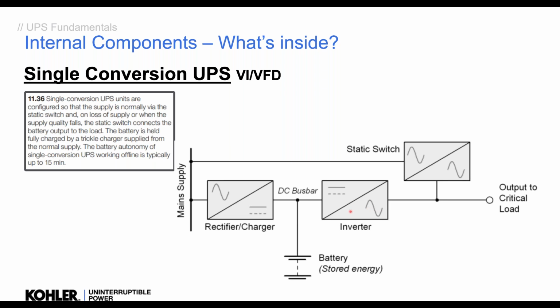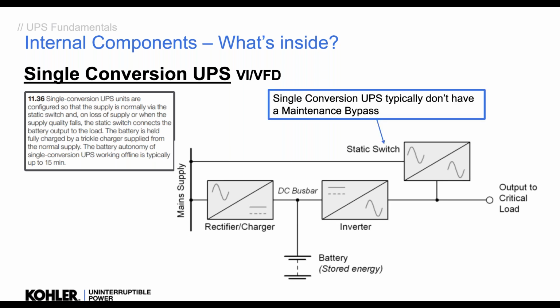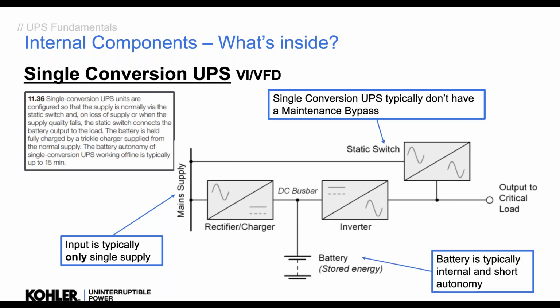Sometimes people refer to them as kicking in when it's required, but these are typically the small UPSs underneath the desks and things like that that you see, short autonomies. Okay, typically don't have a maintenance bypass and typically only can have a single source into them. Okay, so not generally used for life safety, but used in other applications within healthcare. Okay, the battery, like I said, is typically short and internal, doesn't tend to meet the requirements of HTM.